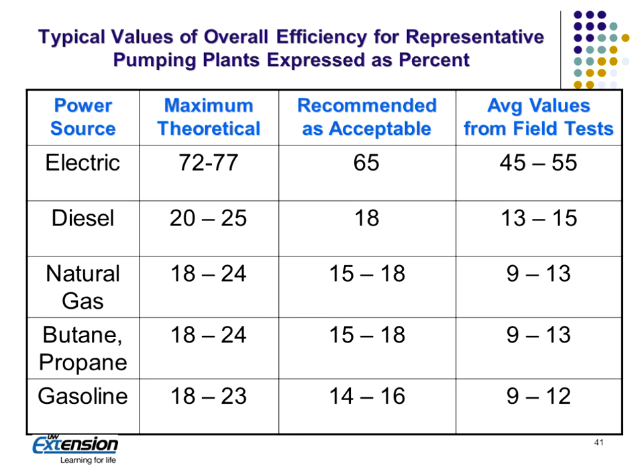Now the overall efficiency is quite different. Electricity, an electric motor of large size, is about 90% efficiency, versus a diesel engine at only 30 to 35% efficiency. And then we have the efficiency of the pump itself. If we base it on the Nebraska pumping criteria, that's about 75%. So if you took 75% times 0.3, you're going to get right in the middle of this, about 22%. So that's the theoretical maximum you can get.